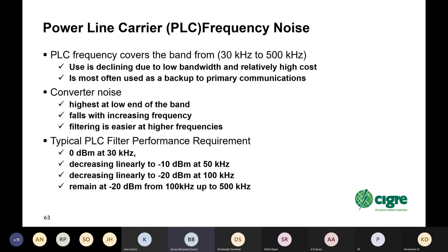Power line carrier interference: power line carrier is declining in use because it has low bandwidth and relatively high cost. It's usually used most often as backup to primary communications, which can be fiber optic or microwave. It's easier to filter at high frequencies, and we've given a typical characteristic for the specification, which corresponds roughly to what you would expect from corona noise from high voltage lines. So basically we're expecting that the DC is not going to exceed corona levels of high voltage equipment.